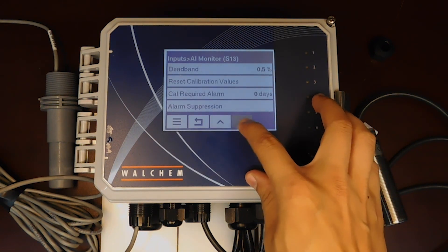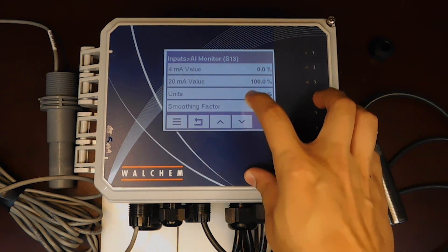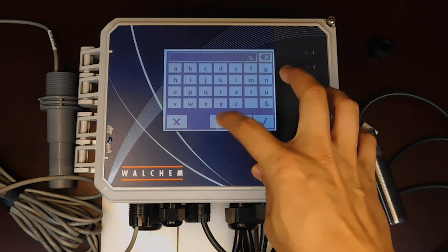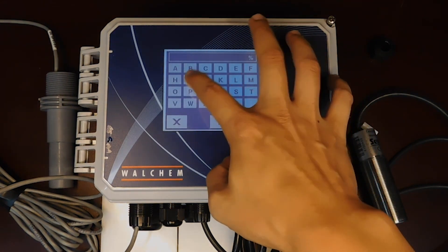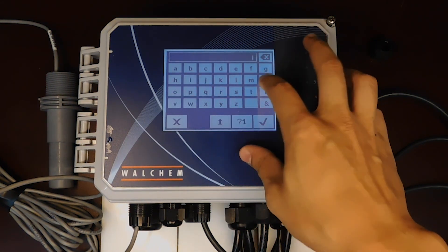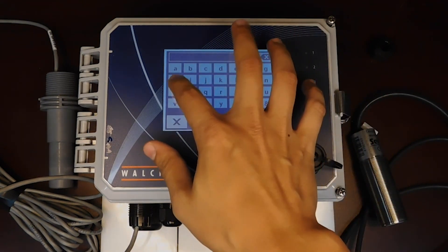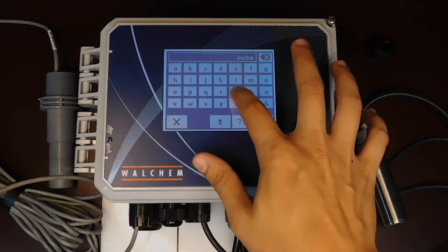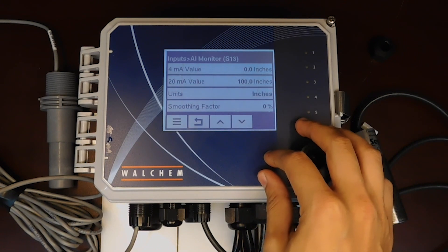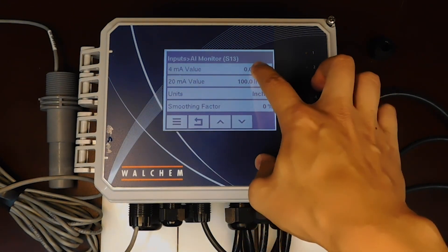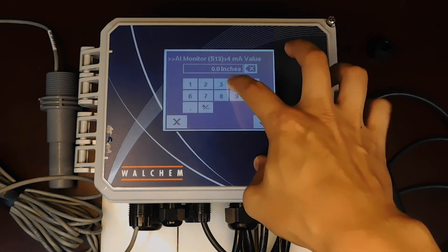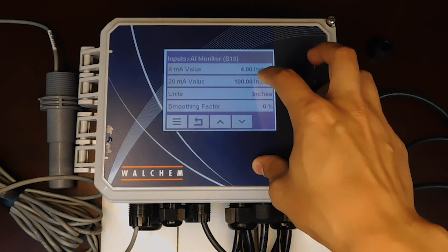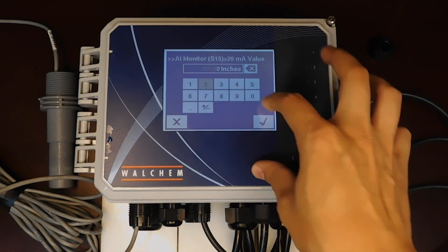We're going to scroll down here. We're going to select units and we're going to put inches. Select check mark. And now we know that four milliamp is four inches and our 20 milliamp value is 20 inches.